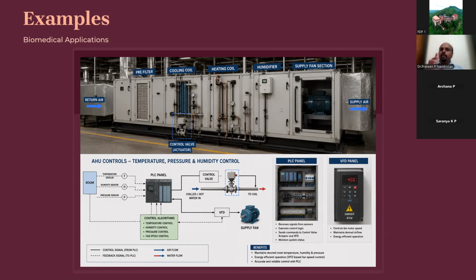We know normal atmospheric pressure is 1 atmosphere. I'm reducing it to 0.9 inside the room and keeping 1.1 at the corridor. Then what will happen? The powder inside will not go from the cubicle to outside. How will I do this with the AHU? I can tell you, this is our supply fan section, which will take air and it goes to the chamber, correct? It goes to the chamber.